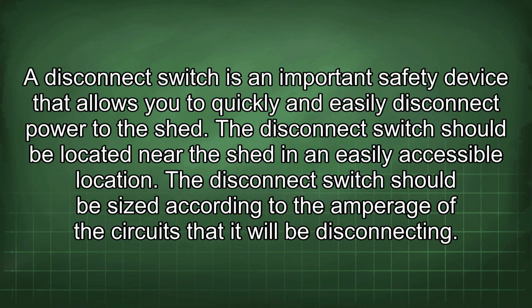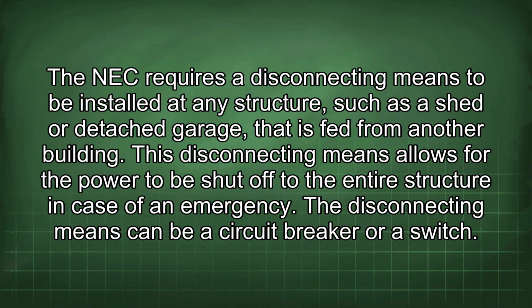A disconnect switch is an important safety device that allows you to quickly and easily disconnect power to the shed. The disconnect switch should be located near the shed in an easily accessible location. The disconnect switch should be sized according to the amperage of the circuits that it will be disconnecting. The NEC requires a disconnecting means to be installed at any structure, such as a shed or detached garage, that is fed from another building.